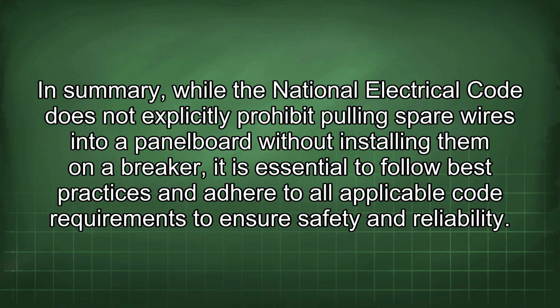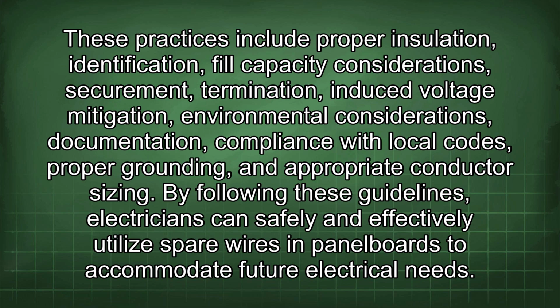In summary, while the National Electrical Code does not explicitly prohibit pulling spare wires into a panel board without installing them on a breaker, it is essential to follow best practices and adhere to all applicable code requirements to ensure safety and reliability. These practices include proper insulation, identification, fill capacity considerations, securement, termination, induced voltage mitigation, environmental considerations, documentation, compliance with local codes, proper grounding, and appropriate conductor sizing. By following these guidelines, electricians can safely and effectively utilize spare wires in panel boards to accommodate future electrical needs.